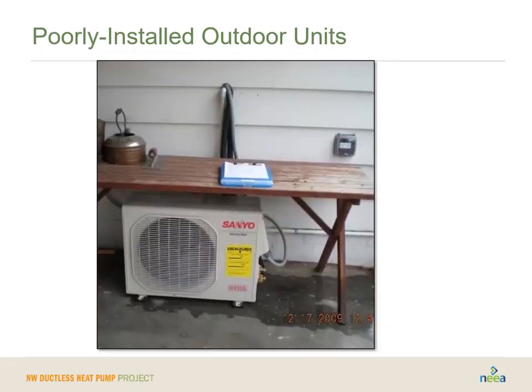Here we have another one. It's installed outdoor, but you can see this is a picture taken in February, so there's some defrost happening, and the defrost is running right onto a walkway where people are likely to walk. And considering that this is happening in February, there is a good chance that could freeze. It also does not appear to be very level. So again, you could risk the longevity of the equipment, and you could cause a slipping hazard here. Finally, it doesn't appear that the penetration through the wall has been adequately weather sealed.